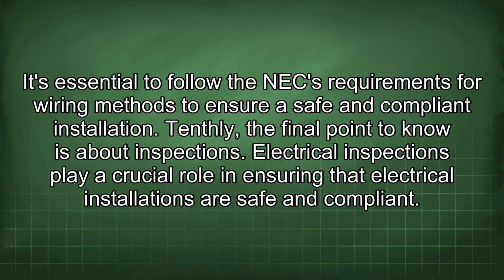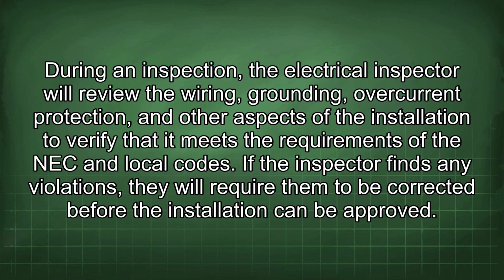It's essential to follow the NEC requirements for wiring methods to ensure a safe and compliant installation. Tenthly, the final point to know is about inspections. Electrical inspections play a crucial role in ensuring that electrical installations are safe and compliant. During an inspection, the electrical inspector will review the wiring, grounding, overcurrent protection, and other aspects of the installation to verify that it meets the requirements of the NEC and local codes. If the inspector finds any violations, they will require them to be corrected before the installation can be approved.